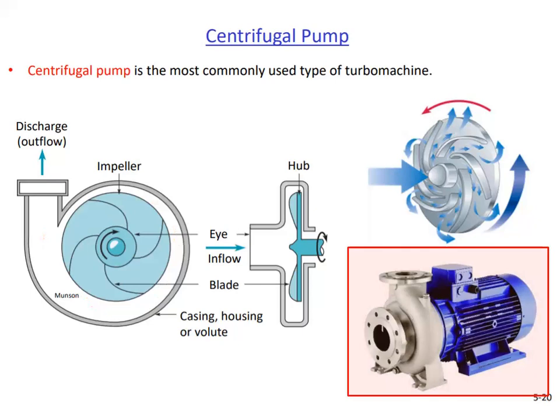This is what a centrifugal pump looks like from the outside. The spiral-shaped volute is easily recognized. The blue part is the electric motor used to rotate the shaft. This is a single suction type centrifugal pump. Fluid enters into the blades only from one side, and the other side of the blades is closed.